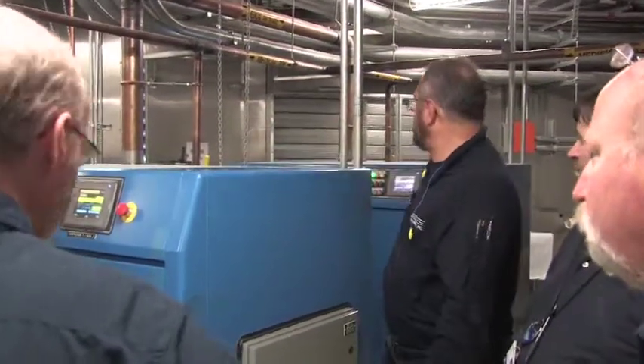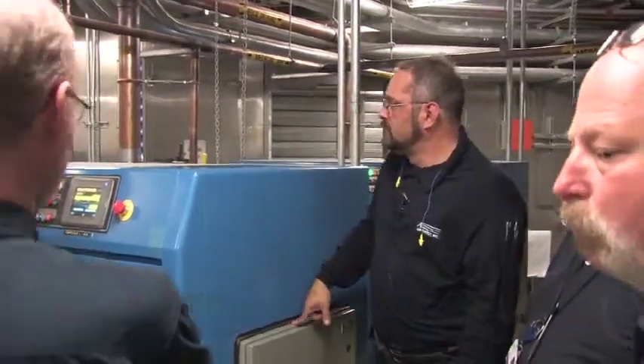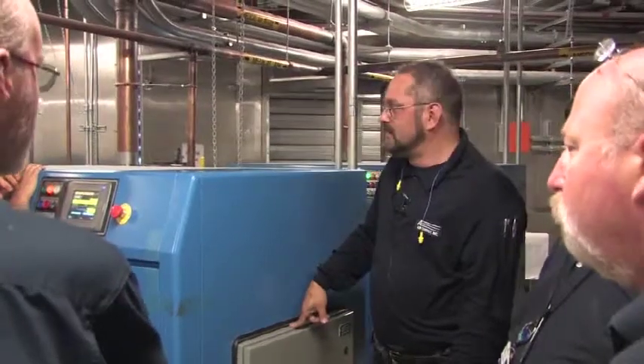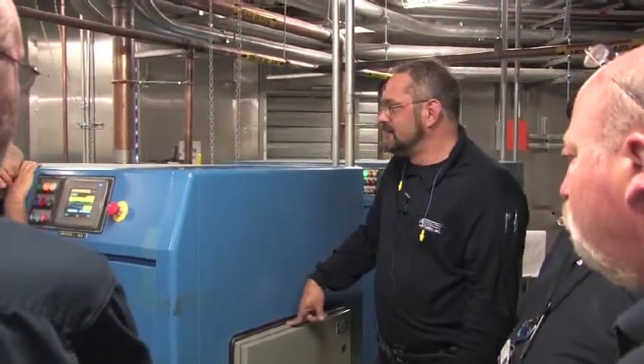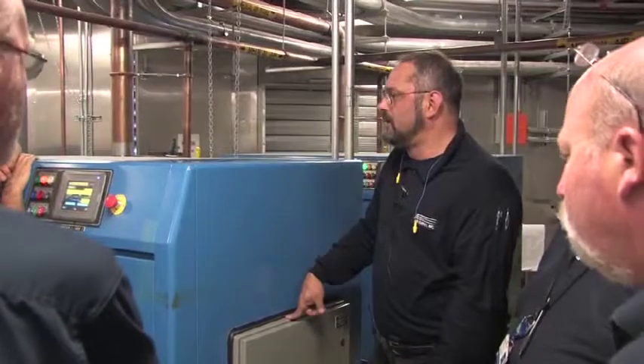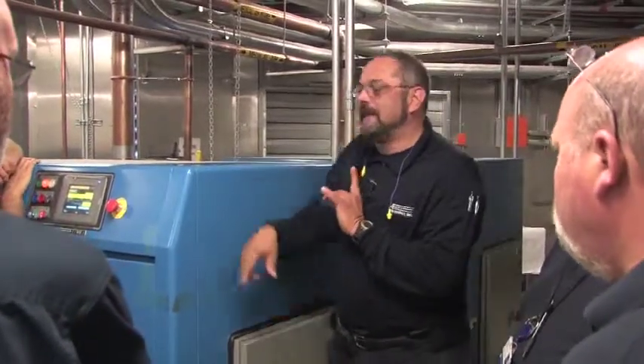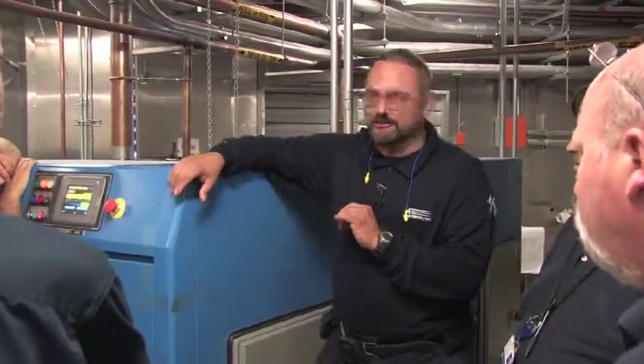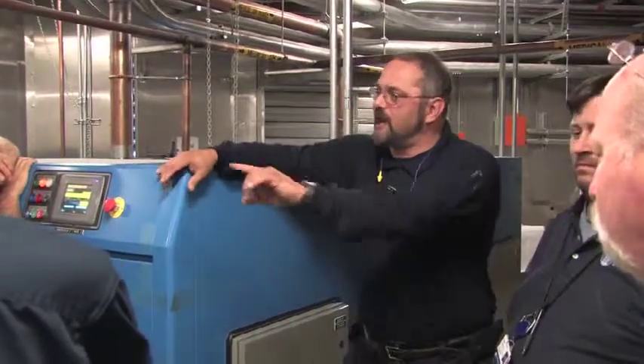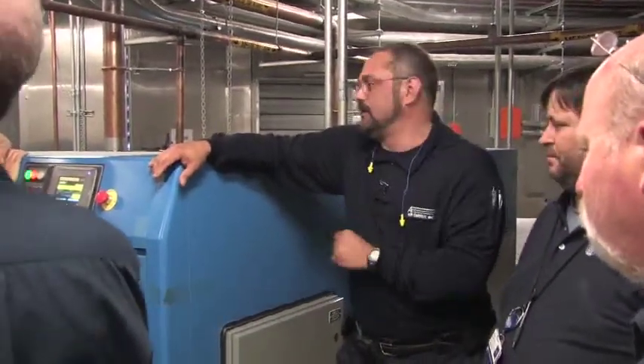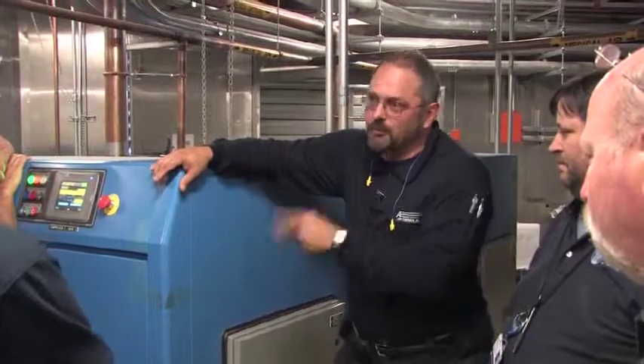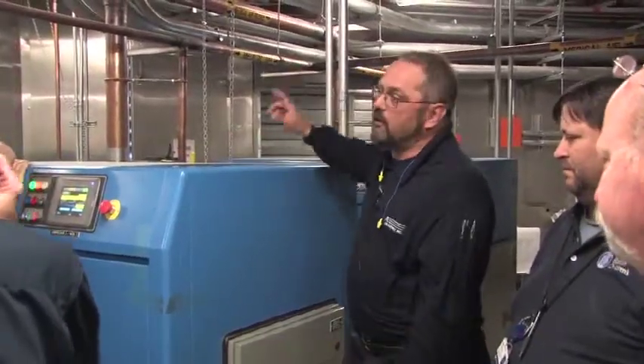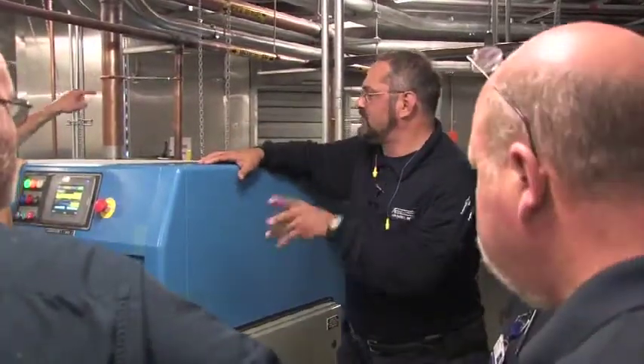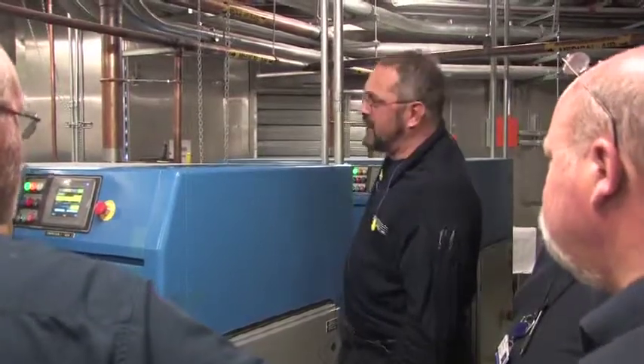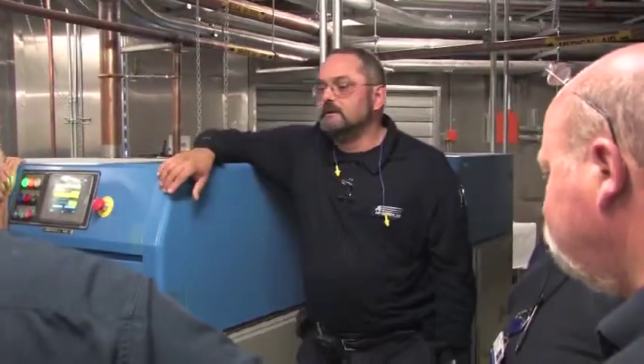the communication from that one is going through the switch in here. It's a powered switch. Kill this, switch loses power. It may or may not, it depends how good the signal is. It may be able to propagate all the way over, it may not. Do I want to gamble on it? No. Put them in local. The only one you can get away with shutting off without switching it to local is Tail End Charlie. The other two are like, whatever, dude.